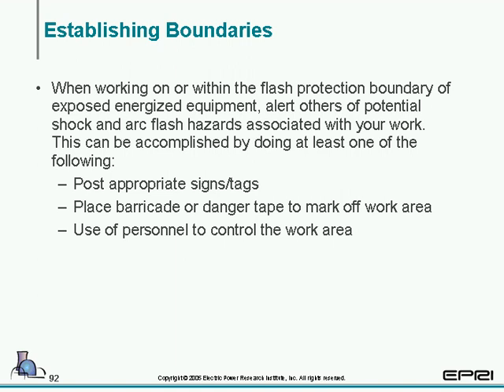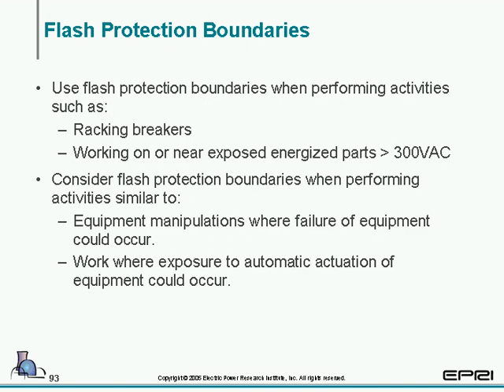When working on or within the flash protection boundary of exposed energized equipment, you should alert others of potential shock or arc flash hazards associated with your work. This can be done by posting signs, placing a barricade or danger tape to mark off the area, or using plant personnel to control the area. Such activities as racking breakers, working on or near exposed energized parts, and you should consider flash protection boundaries when performing equipment manipulations and working where exposure to automatic actuation of equipment can occur.